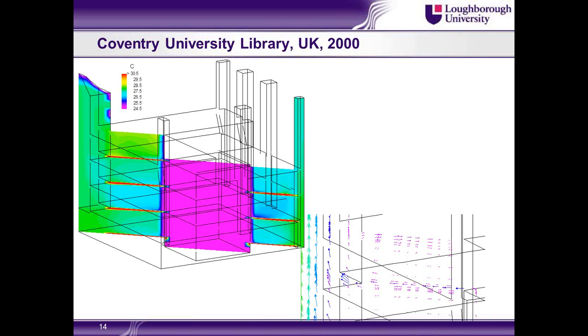And we sized the openings according to the stack force that was acting at that height. So remember those graphs I showed earlier on? The difference between the two graphs increases as you move away from the neutral pressure level. Essentially what that means is we've got a greater driving force on the ground floor relative to the top floor. So these openings down here don't need to be as big as the openings up on the top floor. And we size the openings mathematically based on that to try and get the same flow rate through each floor.